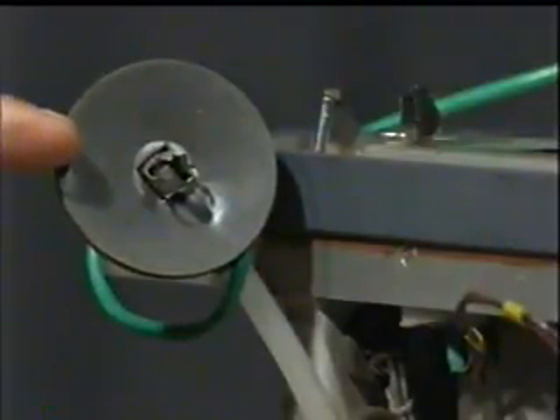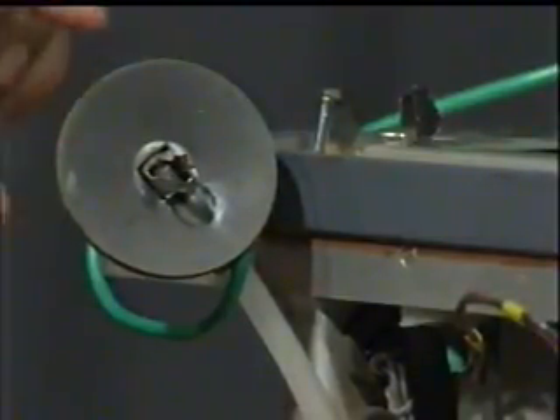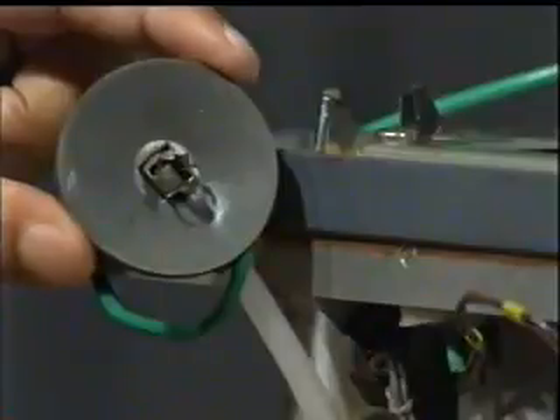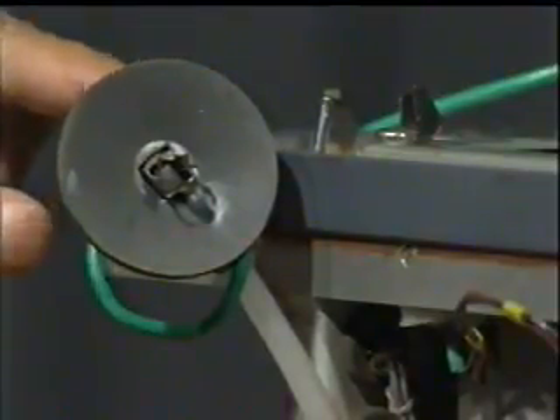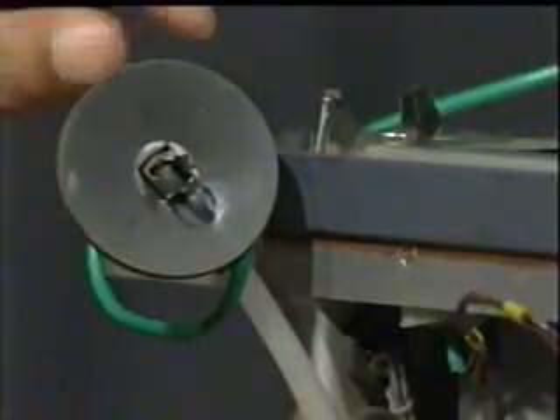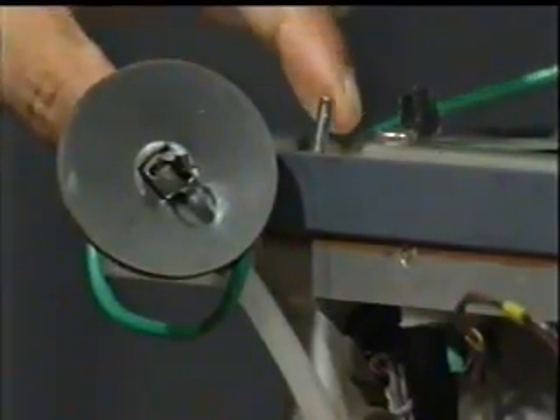And since here is a high voltage which may be dangerous at the time of measurement, therefore make necessary arrangement that during measurement this point should not touch either your body or any point in the oscilloscope. If necessary, make some arrangement to hold the lead. Now switch on the oscilloscope and measure the EHT voltage with respect to ground.